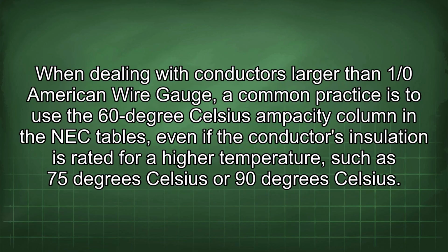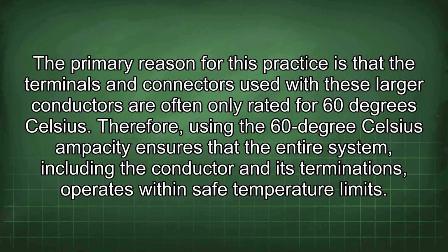When dealing with conductors larger than 1/0 American wire gauge, a common practice is to use the 60 degrees Celsius ampacity column in the NEC tables, even if the conductor's insulation is rated for a higher temperature, such as 75 degrees Celsius or 90 degrees Celsius. The primary reason for this practice is that the terminals and connectors used with these larger conductors are often only rated for 60 degrees Celsius.